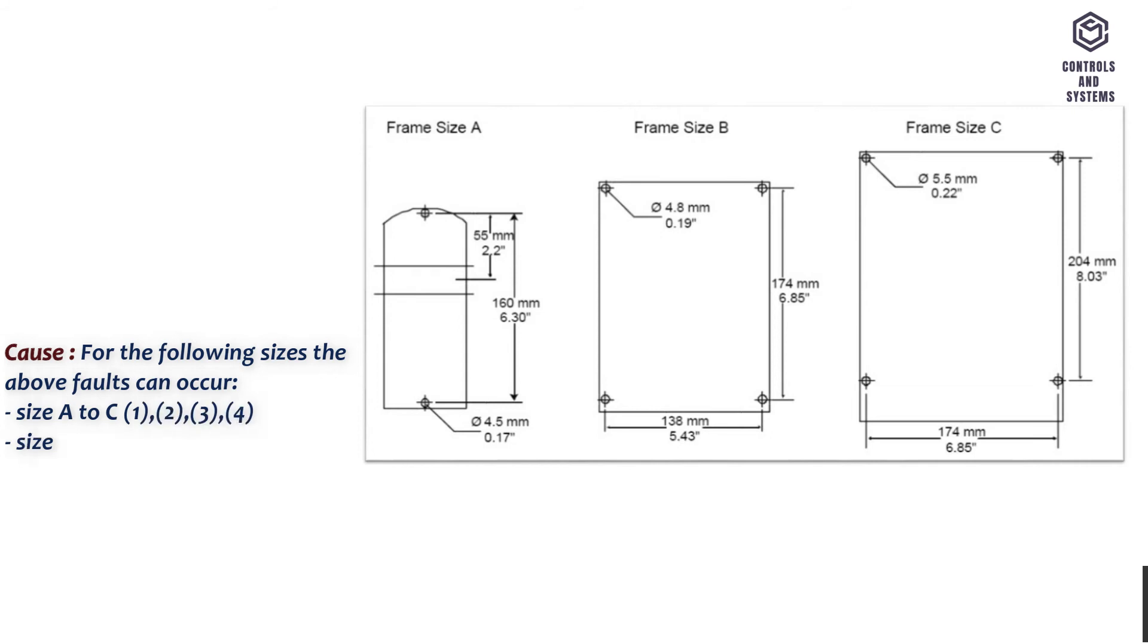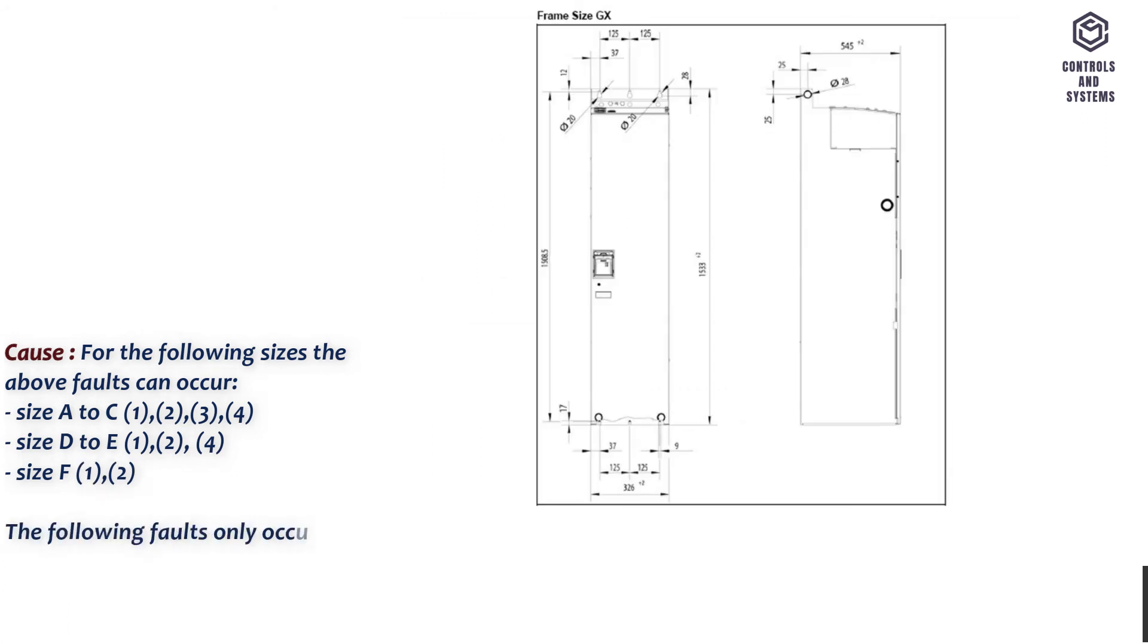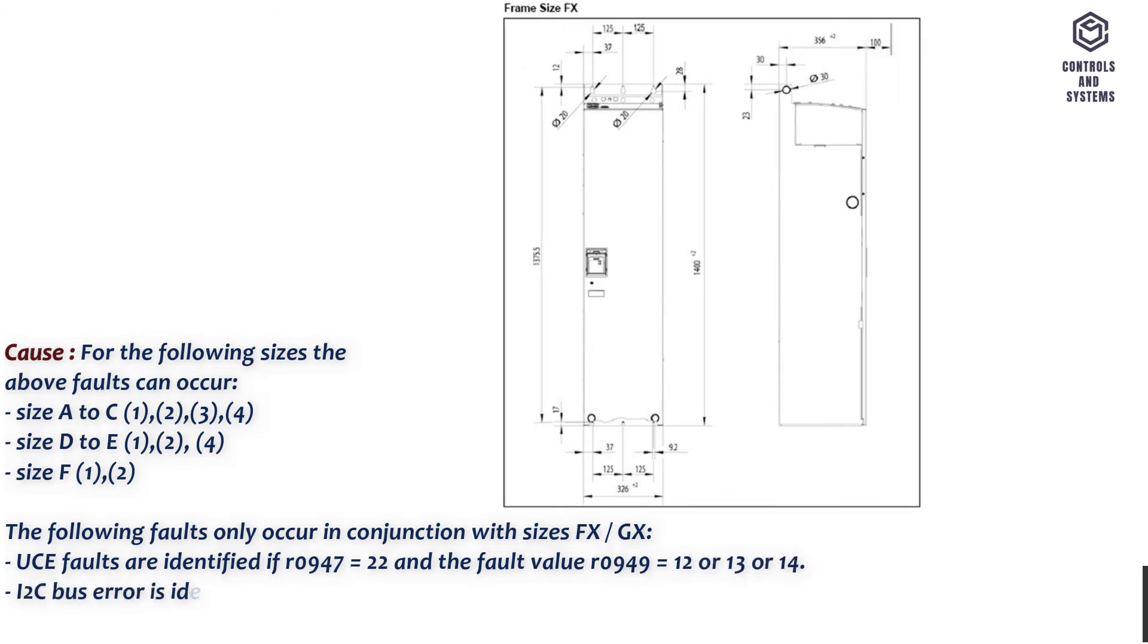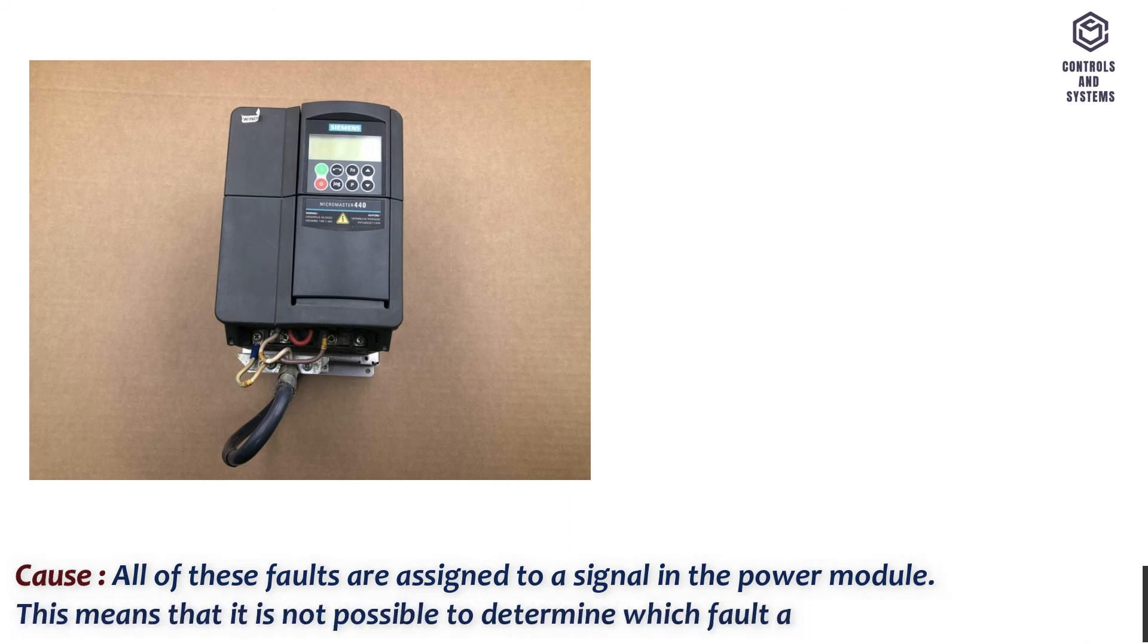Size D to E: 1, 2, 4. Size F: 1, 2. The following faults only occur in conjunction with sizes FX/GX. UCE faults are identified if R0947 equals 22 and the fault value R0949 equals 12 or 13 or 14. I2C bus error is identified if R0947 equals 22 and the fault value R0949 equals 21. Power down and then power up again. Note: All of these faults are assigned to a signal in the power module. This means that it is not possible to determine which fault actually occurred.